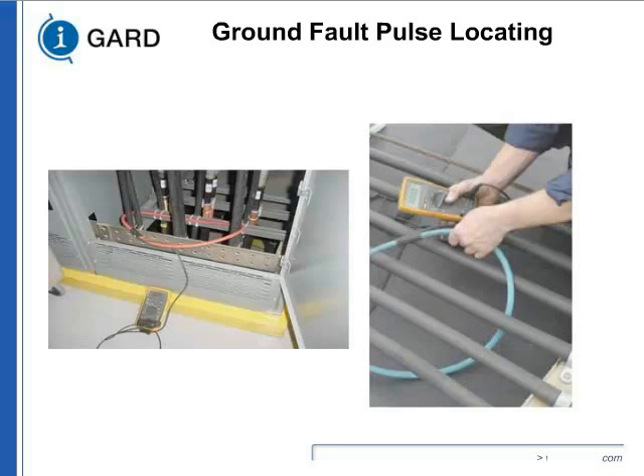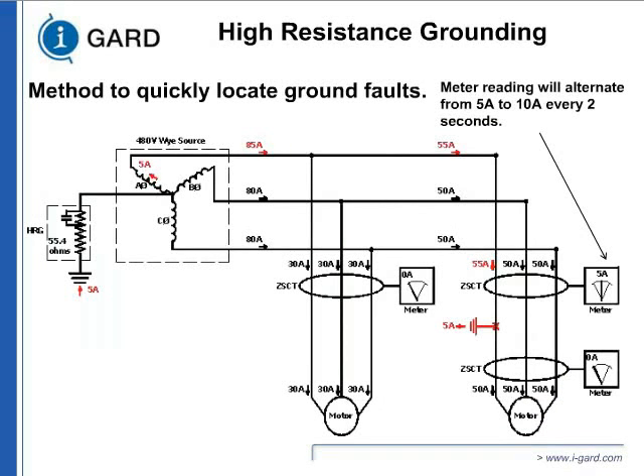So what you do, you identify which circuit it is, you keep on going along with it, and if you notice on the right hand side, when you go past the fault, current will disappear. All you're looking for in the ammeter is a pulse. Actual measuring quantity is not important. As long as the needle is pulsing, you know the ground fault is there.